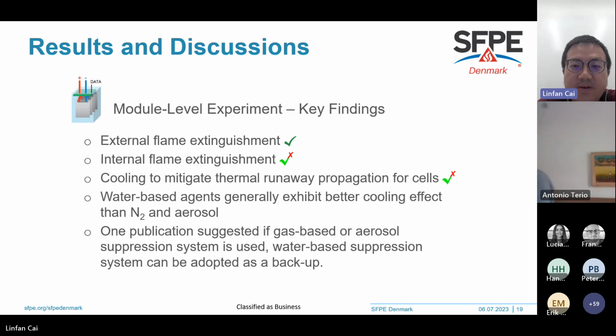Key findings from the module level experiment: external fire extinguishment is totally possible, because if the fire burns out and appears outside the module box, contact with the extinguishing agent will put it out. However, internal fire extinguishing largely depends on whether the agents can penetrate and reach the battery cells. The same applies to cooling. If the extinguishing agents cannot reach the battery cell, there's little or no cooling to the affected cells, so it cannot prevent thermal runaway propagation within the module box.